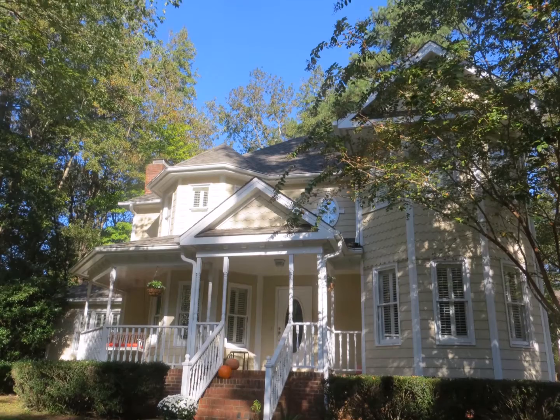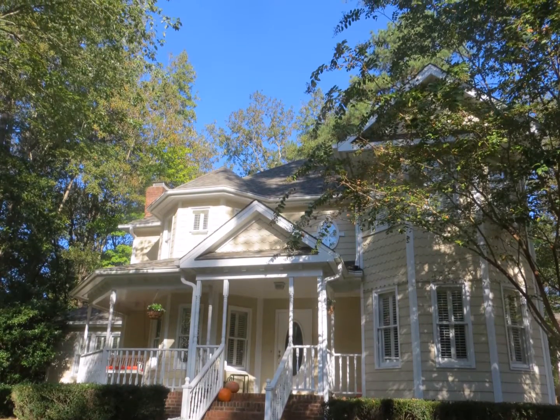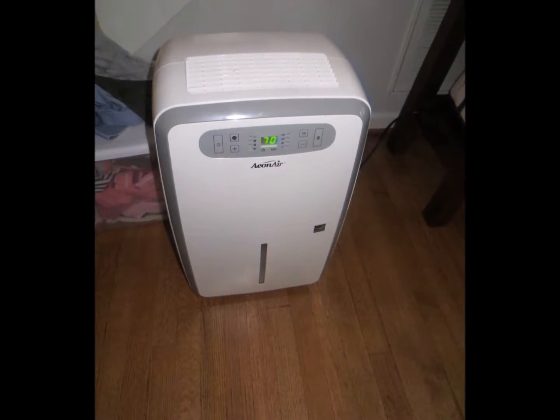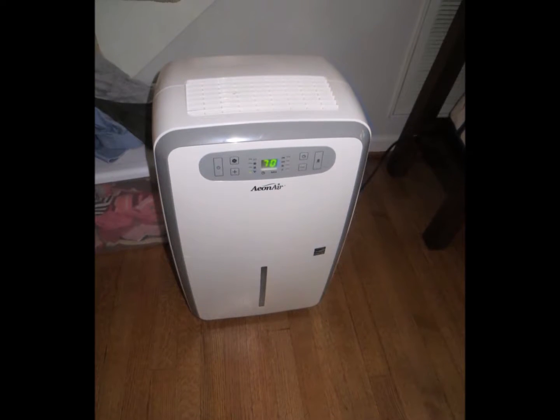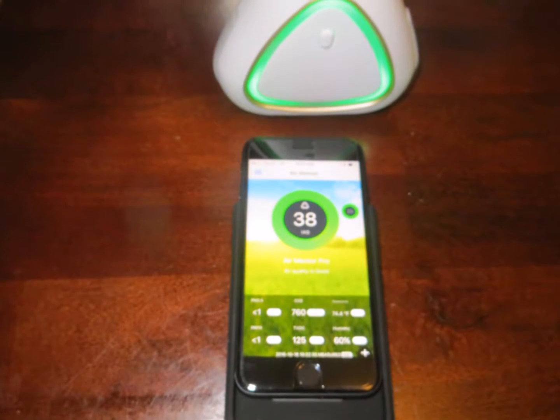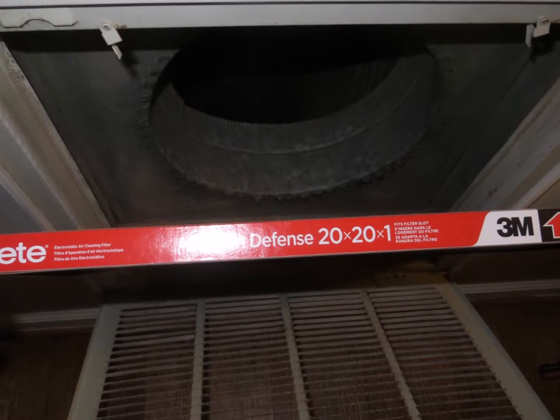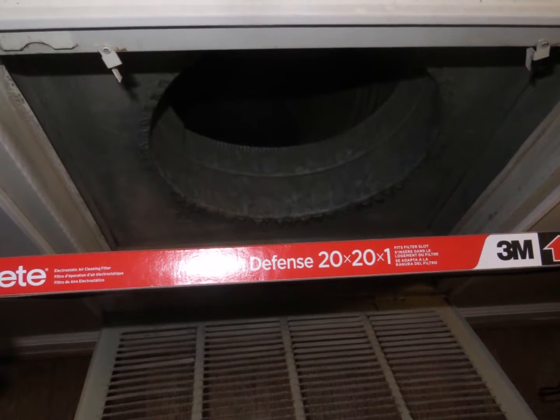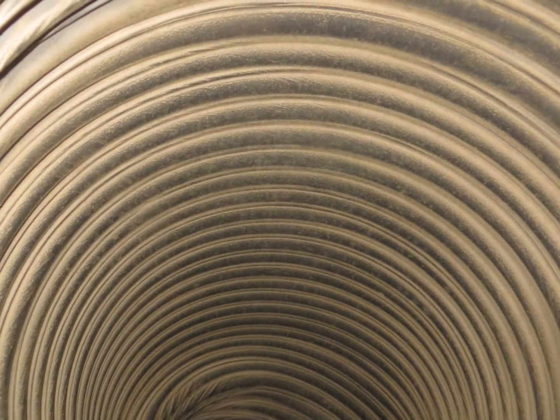Upon entry into the home, I noticed a musty odor, and I see that the dehumidifier, which is too small for the home, showed levels of elevated relative humidity, and that was confirmed by our indoor air quality sensors. It also showed elevated levels of dust. The return is in a good position, but it's slightly blocked. The air filter is a standard filter.